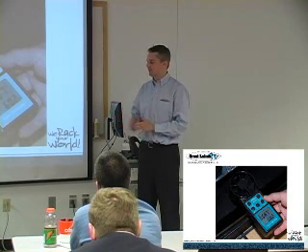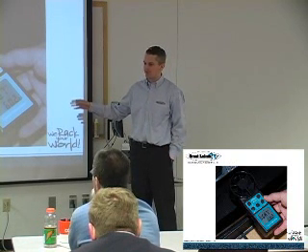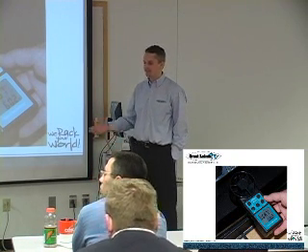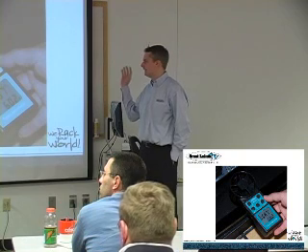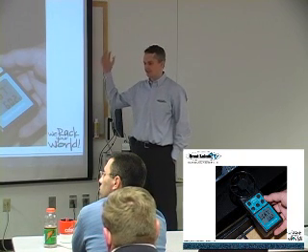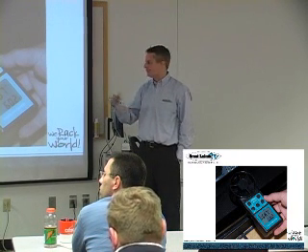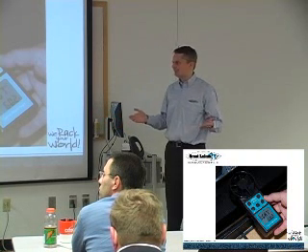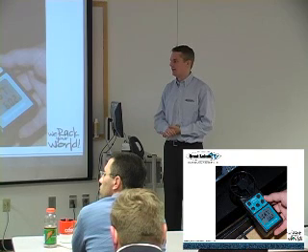If for some reason there was an obstruction that should block a diverter, or if you have a blade server that's drawing 2000 CFM, fans went insane, and it's cutting off the top third, it can still draw through that mesh. And if you maintain a 70-degree ambient air temperature, the ASHRAE TC 9.9 spec, you're still well within.